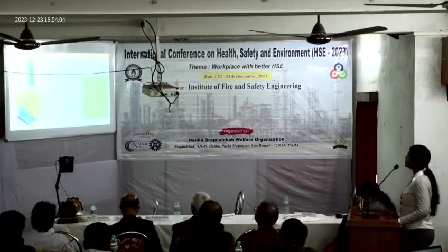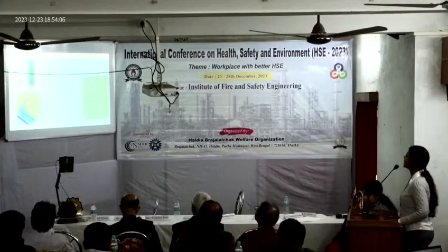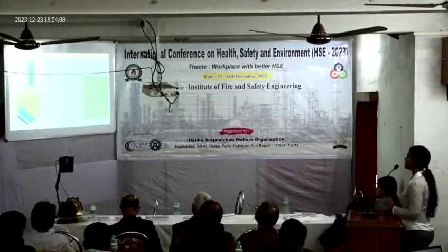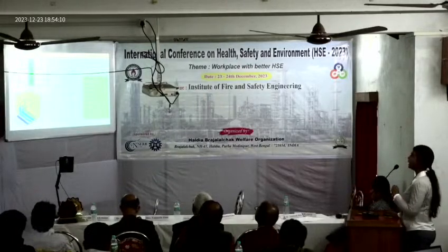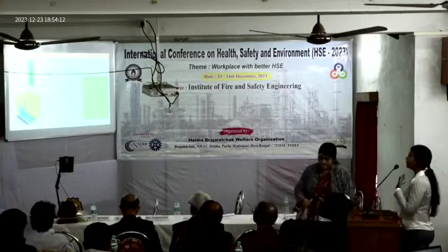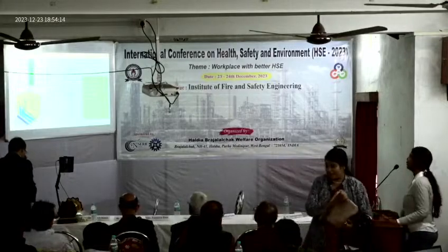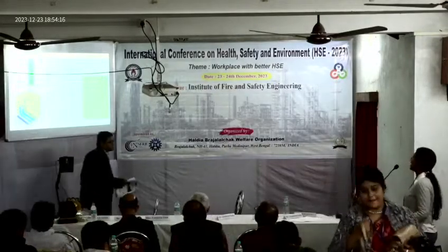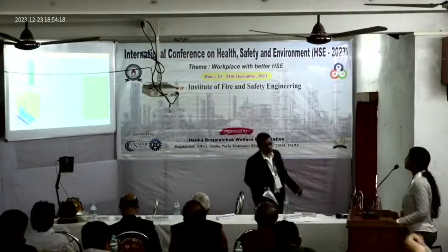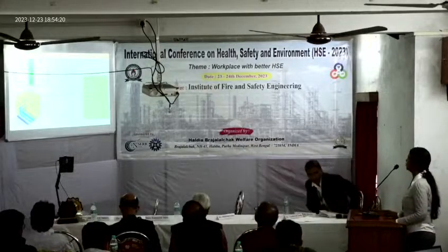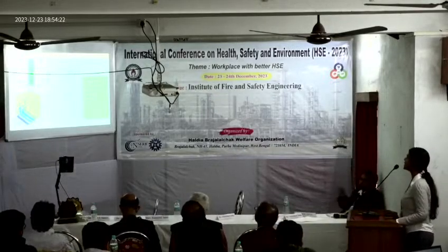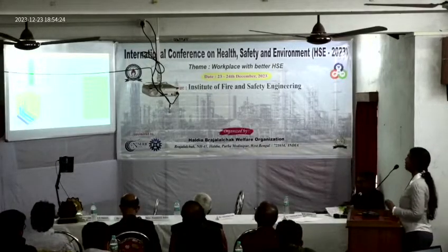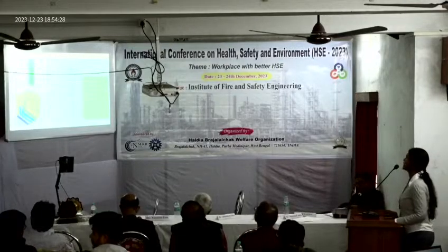The response and recovery time of this sensor is very fast, 1.9 seconds for response time and 23 seconds for recovery time. This is excellent, I can say, for a room temperature sensor. The long-term stability of the sensor was checked for more than 100 days, and it shows almost no degradation in the sensing system.